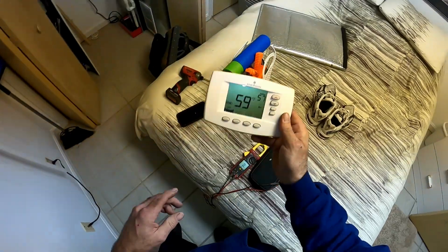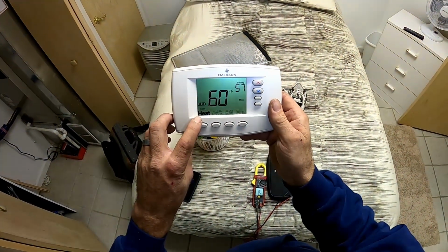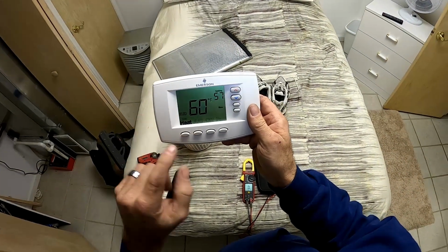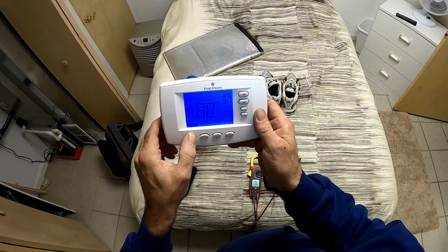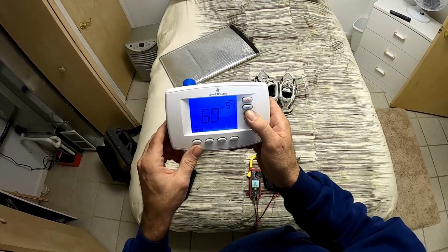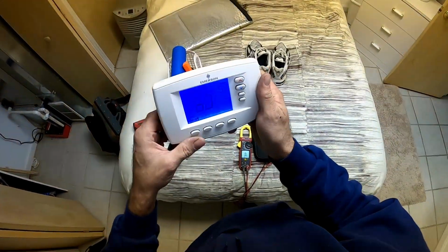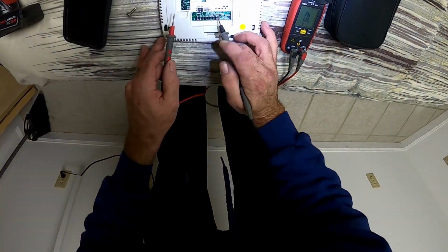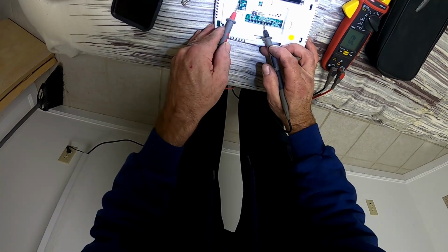Okay, so one thing I noticed is when I looked at the stat before, see how it says aux heat? It didn't have that. So someone in the settings, somewhere in the settings, why is it aux heat? So let's see. Somewhere in the settings, something got screwed up. So I should have RC and a Y call.